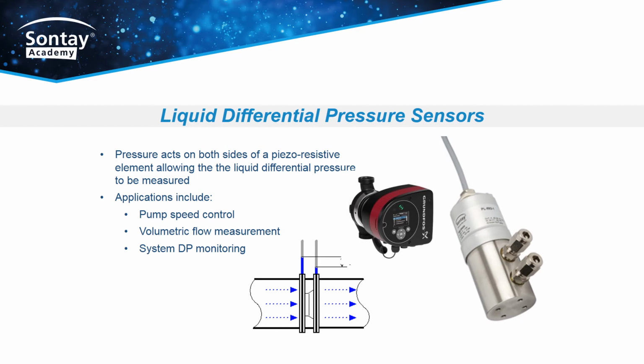The rise in the number of two-port control valves allows the system to be controlled using a differential pressure sensor to maintain a volumetric flow through the system matching the load. As the two-port valves close down, the volumetric flow reduces and the pump differential pressure increases. By sensing this increase in pressure differential, the pump can be slowed down to match the operating point of the system. As with air DP sensors, liquid DP sensors can be attached to Venturis or orifice plates to ascertain volumetric flow based on variances in differential pressure.